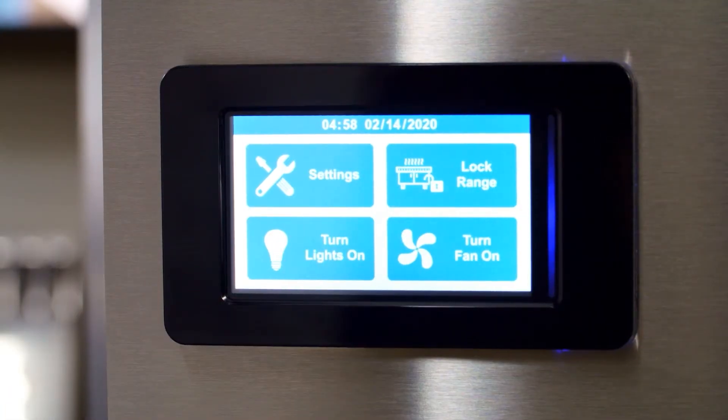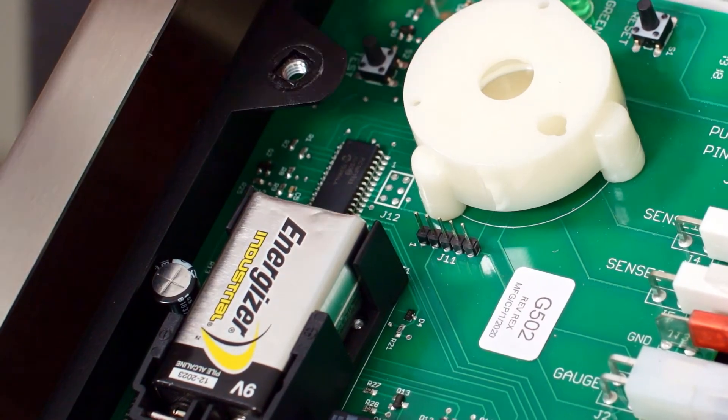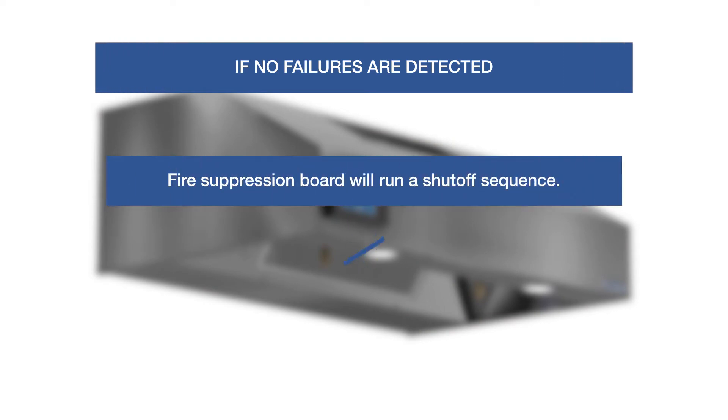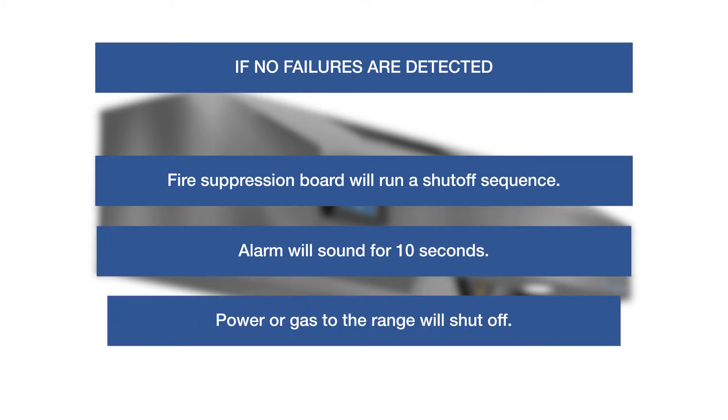For final verification, unlock the range via the touch screen, turn on a range burner, then push and release the test button. If there are no failures detected, the fire suppression board will run a shutoff sequence. The alarm will sound for 10 seconds and shut off power or gas to the range, followed by a chirp every minute. This allows complete system verification, but without the chemical agent release.